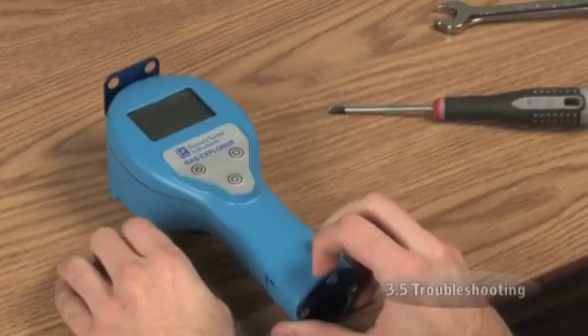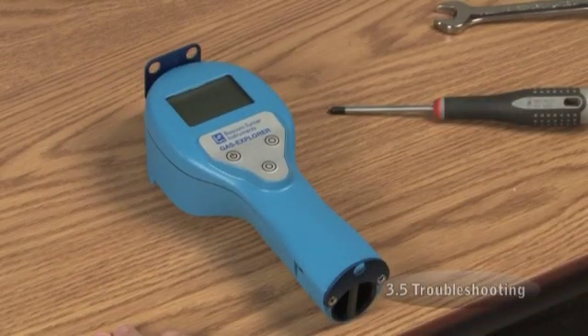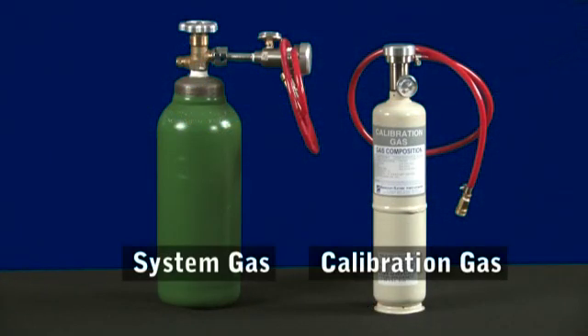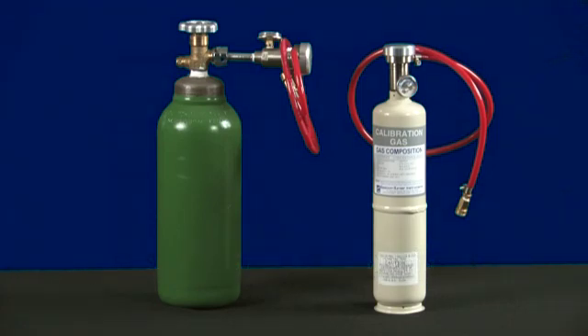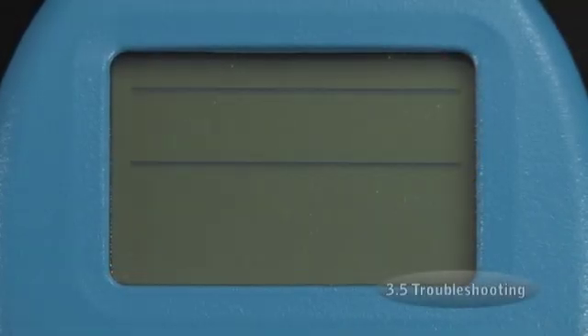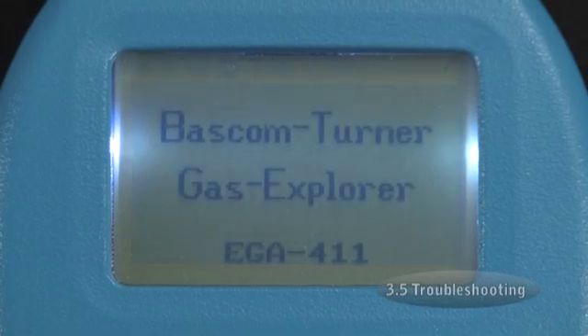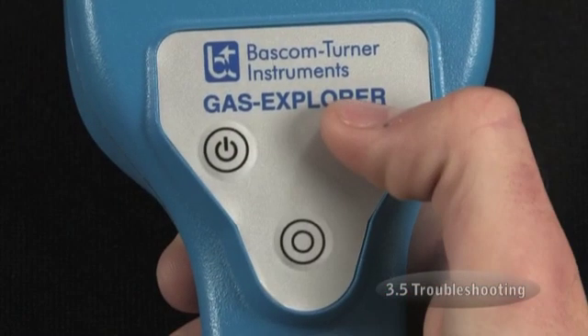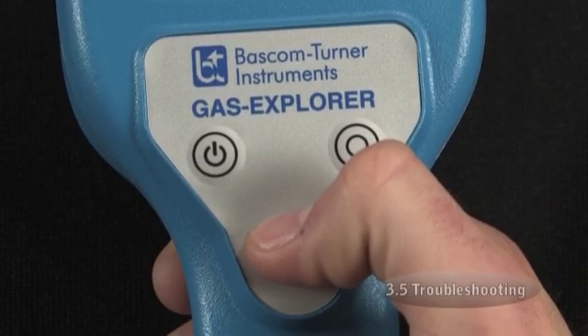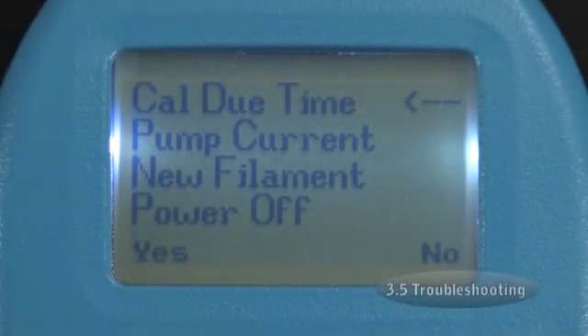You will now need to run a new filament routine. The new filament routine is required whenever a new sensor is installed in an Explorer or a current sensor needs a full 2-gas calibration using 100% methane or system gas and Bascom-Turner's methane CO calibration gas. To run this routine, power on the Explorer, and as soon as the pump is heard, press the right and center buttons within 1 second of each other. This will cause the Explorer to enter the Setup menu.